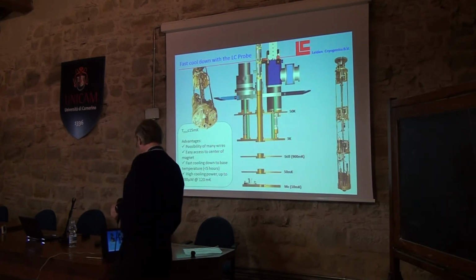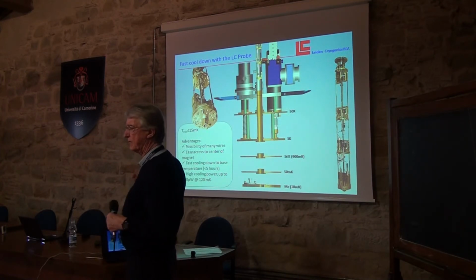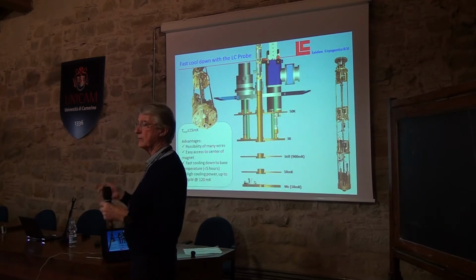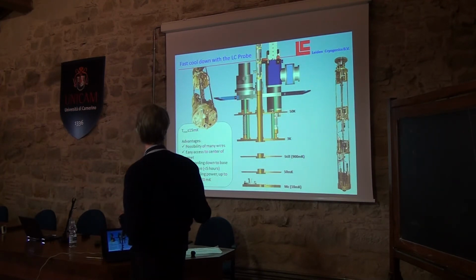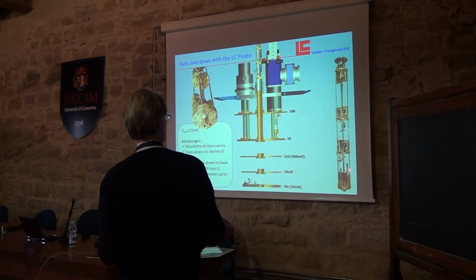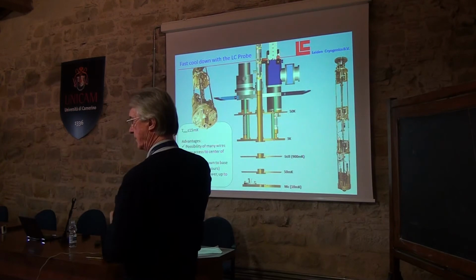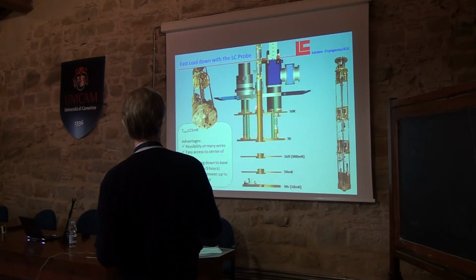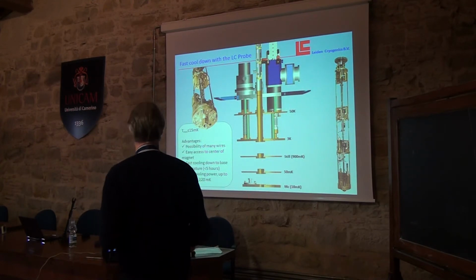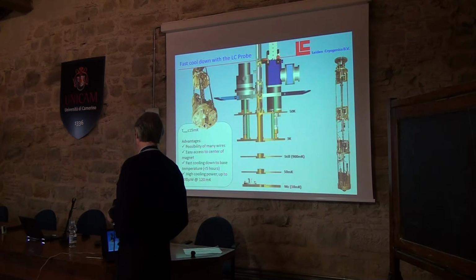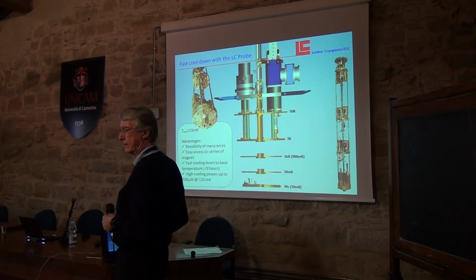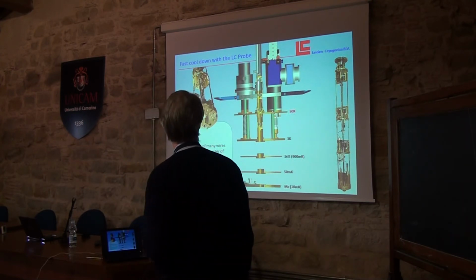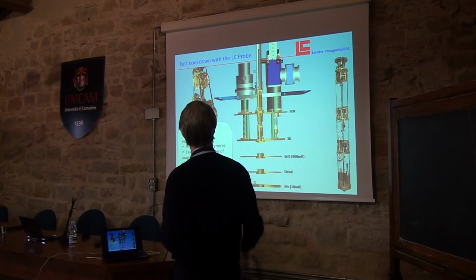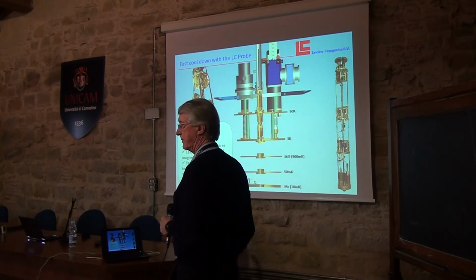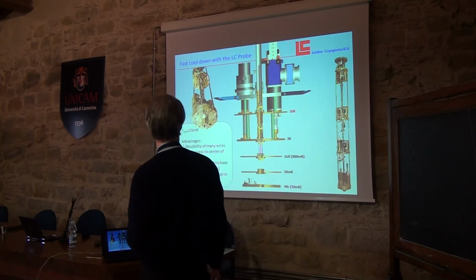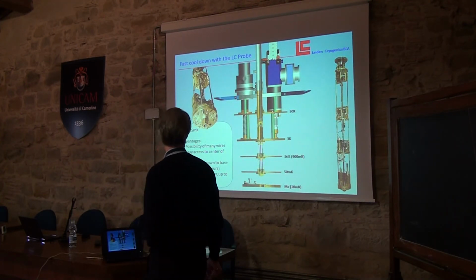An important development is the top loading probe, because these machines take roughly 2 days to cool down, so you don't want to wait a long time. So when the machine is cold, you can put your samples on a top loading probe like this, which has mechanical contacts. When you pull on a rod, they expand and make contact to the various temperature plates. So this allows you to change samples in 3 hours instead of waiting days. So you stop at different stages of the refrigerator, 15 minutes each, and then at the end you have your sample at base temperature.